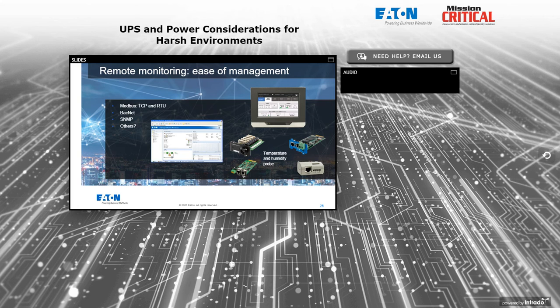But an awful lot of our clients are not physically present to interact with their UPS, so they need to be able to get good, reliable, accurate information from anywhere, including their laptop at home if it happens to be on the weekend or something like that. So communication cards that snap into the UPS and have multiple ports so I can install multiple communication cards. Maybe I have 2 different networks on site and I want to be able to communicate over each of those independently in case one network goes down. So the ability to have multiple communication cards in a given UPS is important.